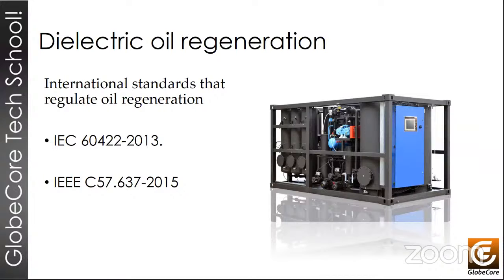The process, like I say, can take a long time because regeneration is akin to microfiltration, and microfiltration tends to take long. Even if we have sorbent columns with a 130 kilogram load of sorbent, we'll be able to filter around 100 liters of oil per hour on average. So this is an operation that should be planned ahead so that we ensure uninterrupted operation. Next, please.